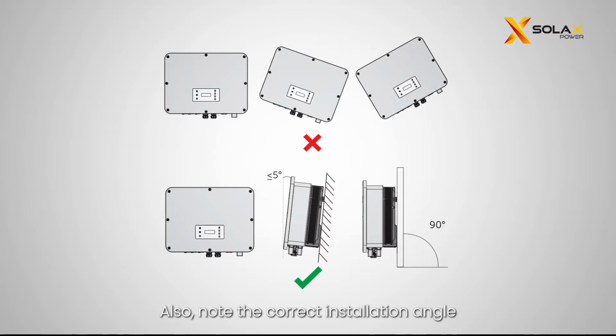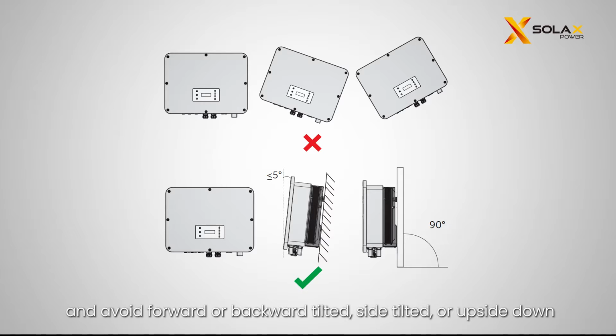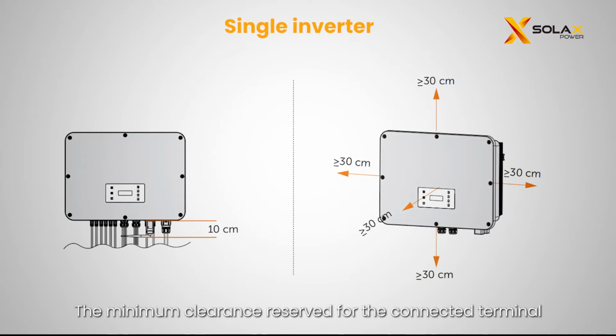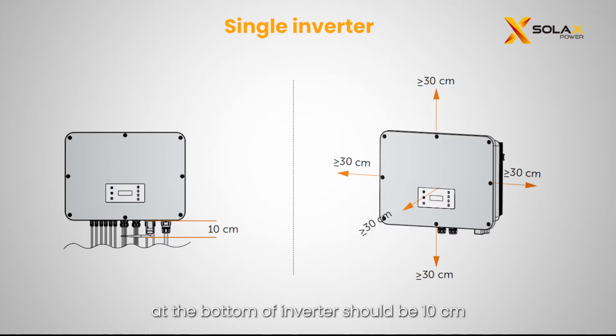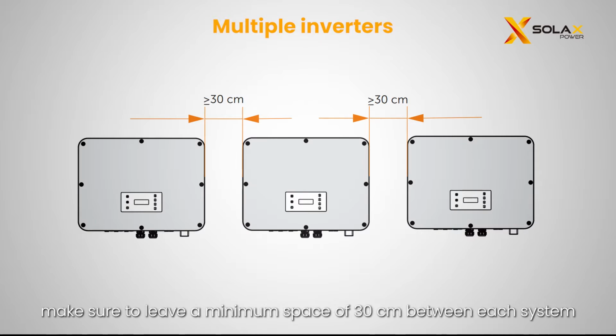Also, note the correct installation angle. Install the inverter at a maximum back tilt of 5 degrees and avoid forward or backward tilted, side tilted, or upside down. The minimum clearance reserved for the connected terminal at the bottom of inverter should be 10 centimeters. For multiple systems installation, make sure to leave a minimum space of 30 centimeters between each system.